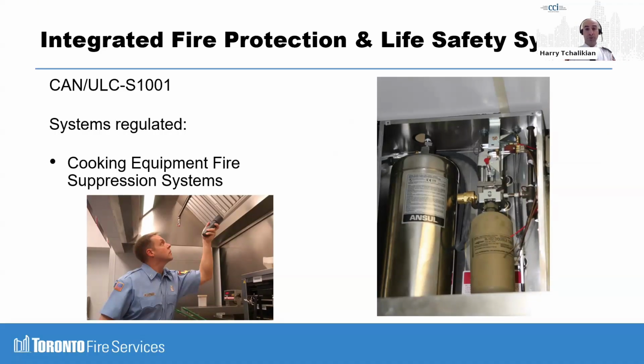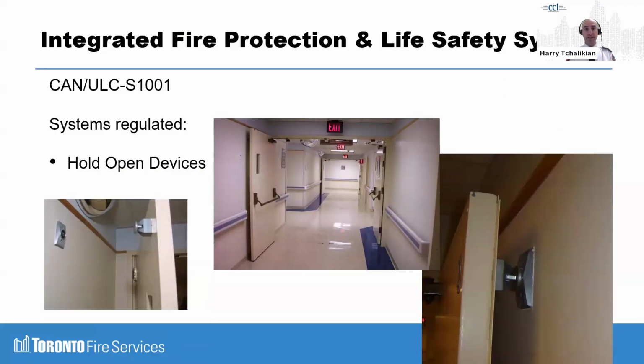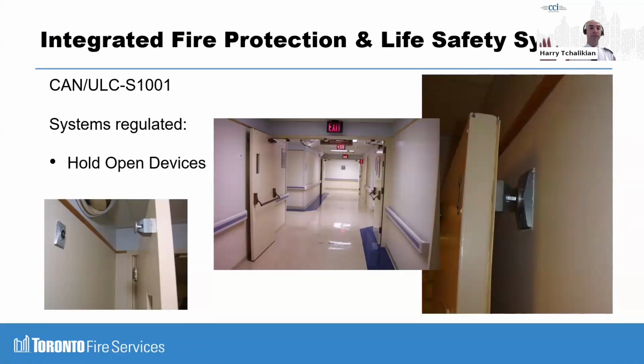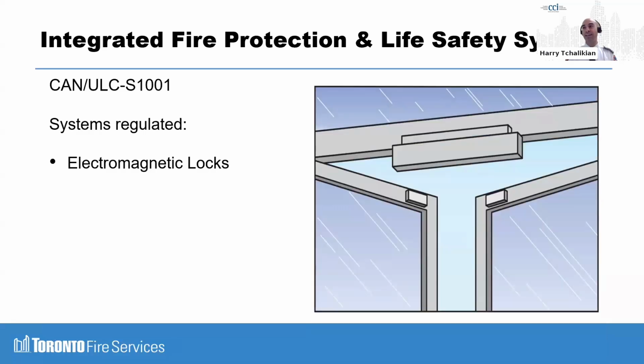Some of the other simple ones: hold open devices, you're already doing this. Now, the tech company can upsell you to make sure that the door actually closed. Same thing with maglocks. You should have already been doing this as part of your annual: did the magnet release and did the door open? But this is already part of your annual, so you should have already addressed 100% of this.